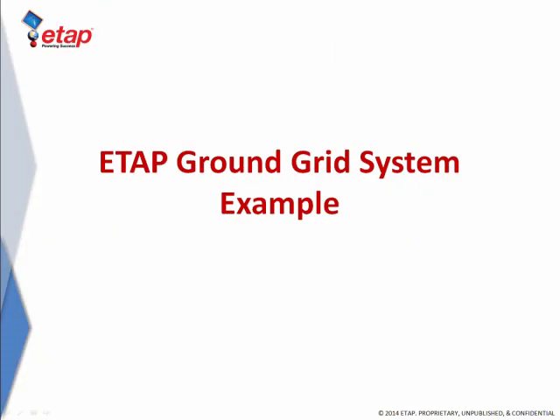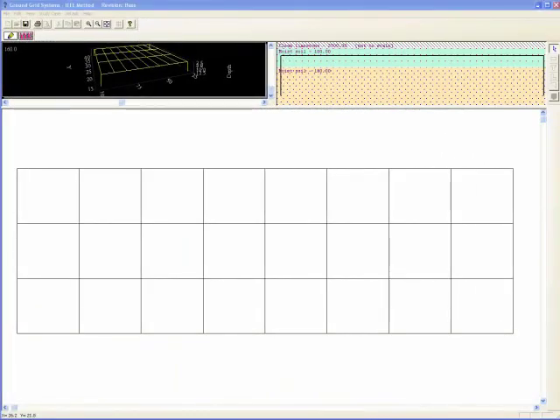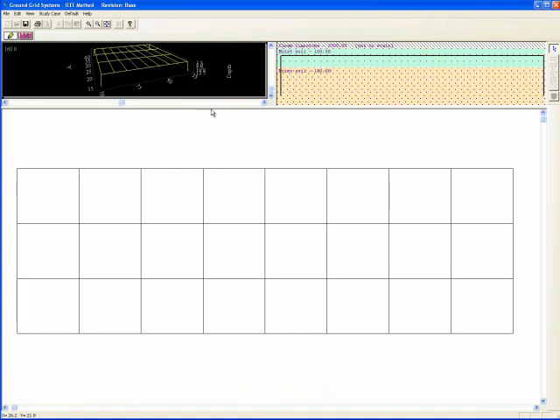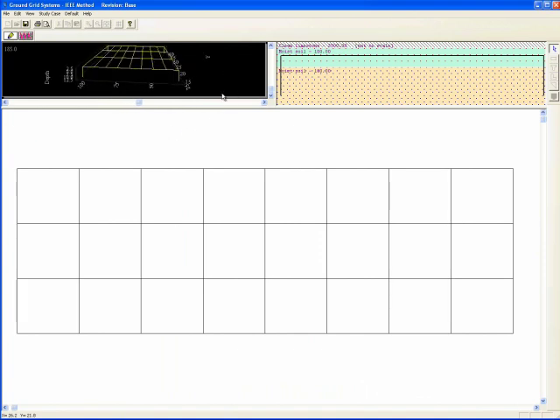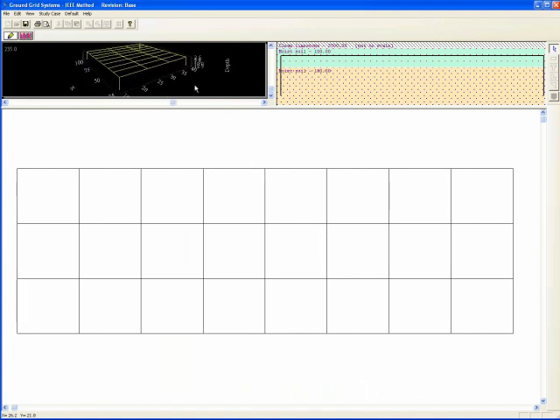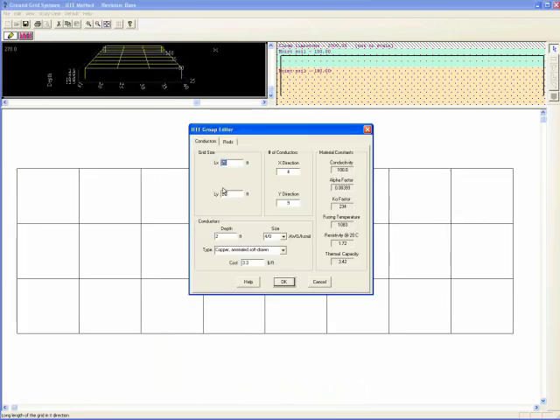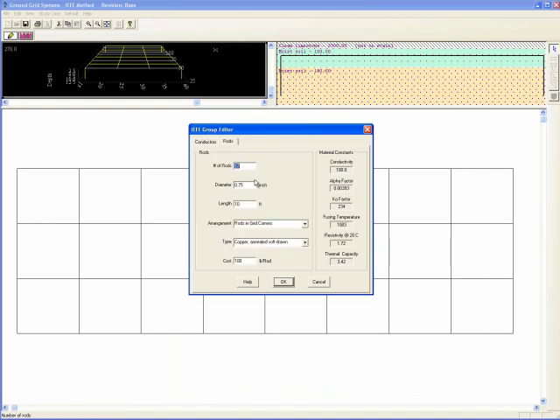Let's see the advantage of ETAP ground grid module through an example. In this example, we've designed a 4 by 9 conductor rectangular shape ground grid with 4 number of rods placed at the corners. The design includes the types and costs for individual conductors and rods.